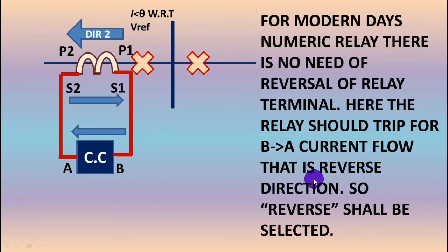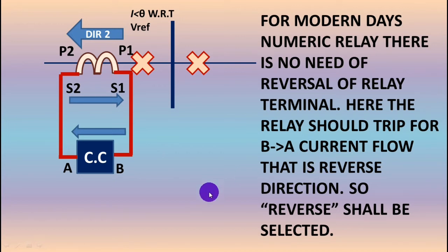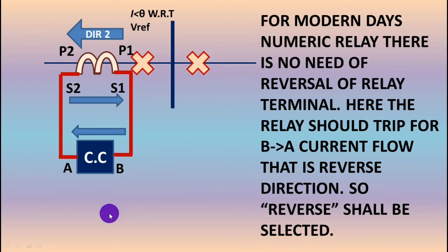For modern numeric relays there is no need to reverse the relay terminals. This relay should trip for B-to-A current flow — that is, the reverse direction has to be selected. For modern numerical directional relays there is a selection for forward tripping or reverse tripping. If you set reverse tripping it will trip for current flowing from B to A; if you select forward tripping it will trip for current flowing from A to B. For this particular case we have to select the reverse setting.